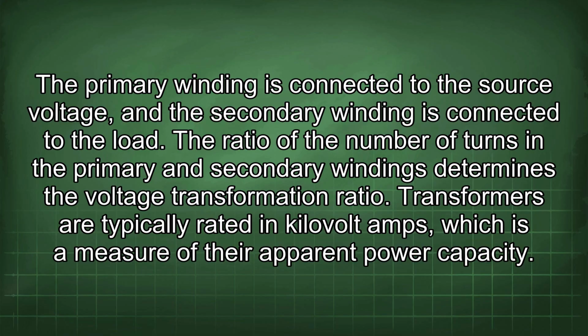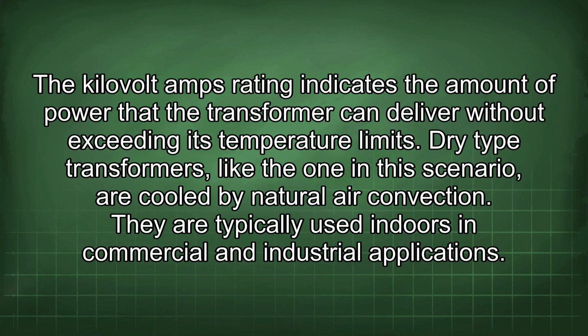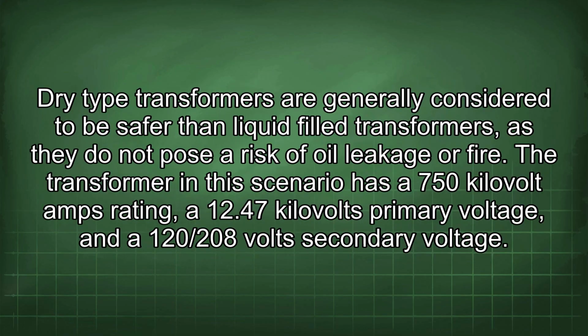Transformers are typically rated in kilovolt amps, which is a measure of their apparent power capacity. The kilovolt amps rating indicates the amount of power that the transformer can deliver without exceeding its temperature limits. Dry-type transformers, like the one in this scenario, are cooled by natural air convection. They are typically used indoors in commercial and industrial applications. Dry-type transformers are generally considered to be safer than liquid-filled transformers, as they do not pose a risk of oil leakage or fire.